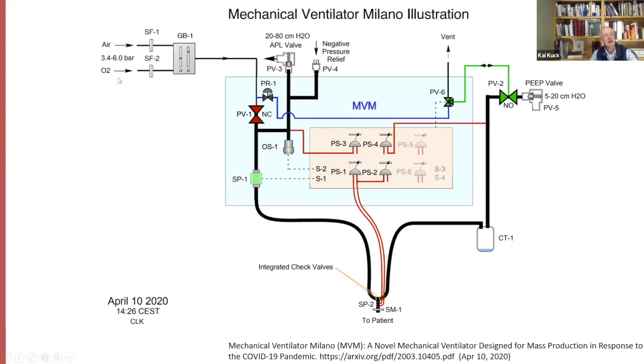We have our air and oxygen coming in from the wall, 3 to 6 bars. I don't know off the top of my head how to calculate this back, but in our hospital, our wall pressures are around 50 psi. You have flow meters here to dial in what you need. It goes through a proportional valve. So that's your inhalational valve, and that allows you to create those flow waveforms that you need. There's a flow sensor here that allows you to know how much gas you're actually delivering. The gas goes down here to the patient.